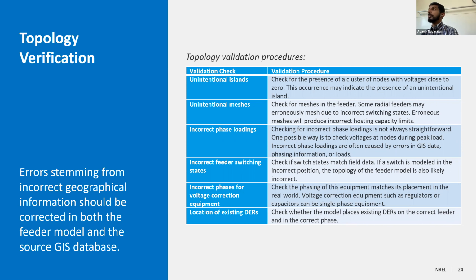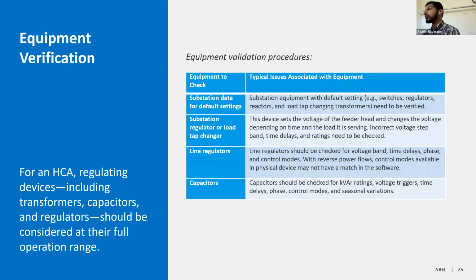The second set of issues you can look at is equipment verification. You can look for substation data and default settings. Make sure you have the right model of substation transformer. Should this be a load tap changer? Should this be a fixed transformer? Take a look at it. Make sure you have the right impedances modeled. Make sure you have the right voltages.